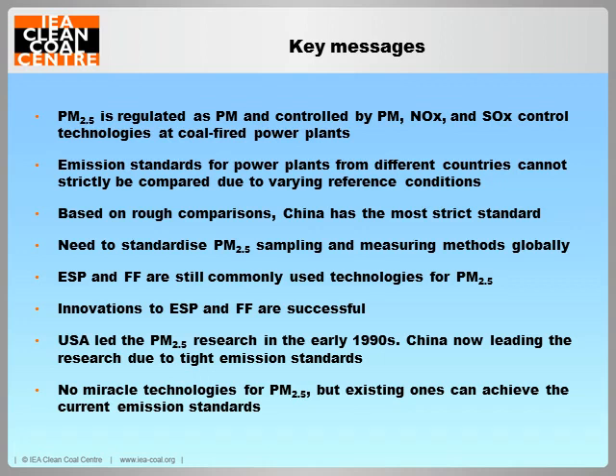To summarise, PM2.5 emissions from coal-fired power plants are regulated by PM, SOx, and NOx emission standards, and controlled by PM, SOx, and NOx control technologies. When comparing different countries' PM emission standards for coal-fired plants, attention should be paid to the reference conditions, measurement unit, time averaging period, and the definition of new plants. Based on rough comparison, China has the strictest PM emission standards.